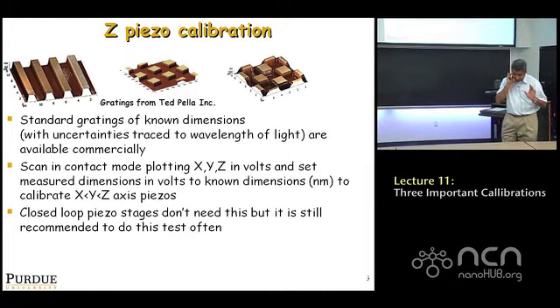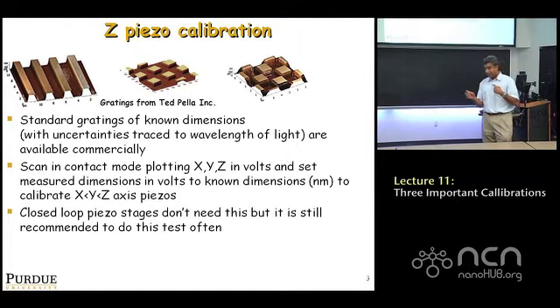Now, having said that, there are some new technological developments in AFM. One is the use of closed-loop piezo stages. If you buy new AFMs, you're always going to get closed-loop piezo stages. What closed-loop piezo stages do is they have built inside them a sensor that detects how much the piezo is actually moving, right? So you apply a voltage, but it actually detects in nanometers how much is actually moving. So it's a closed-loop system. So you don't have to apply a voltage and try to figure out how much it moved. Rather, the system feedback loop is doing it for you. Of course, this makes life easy.